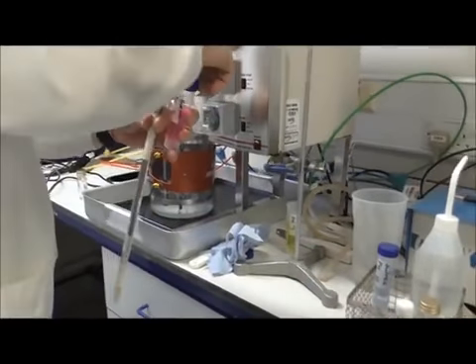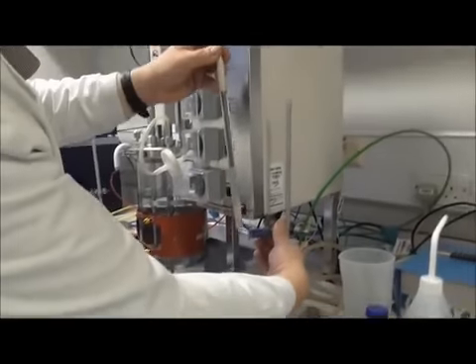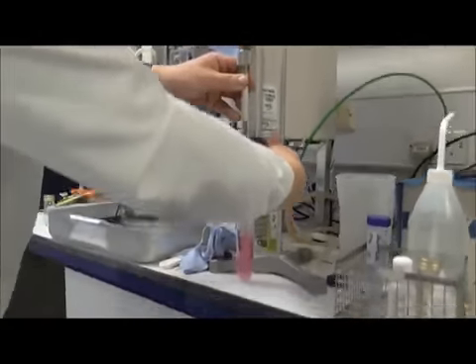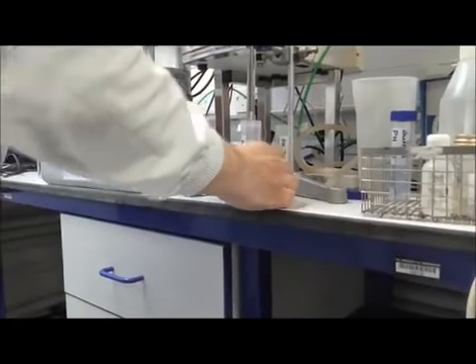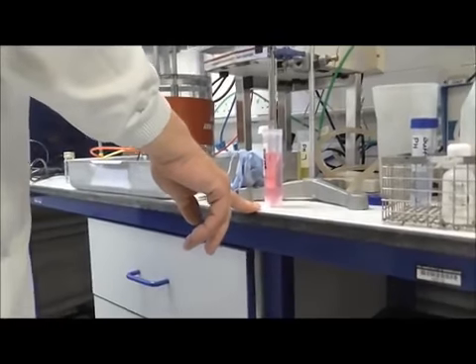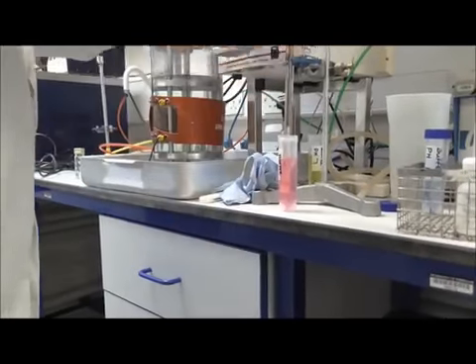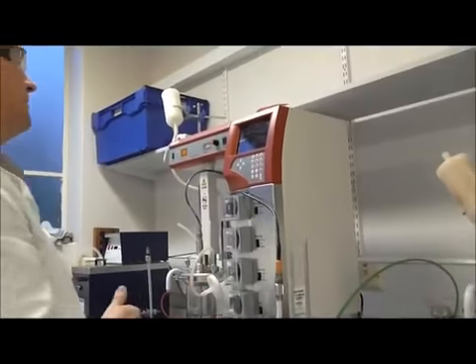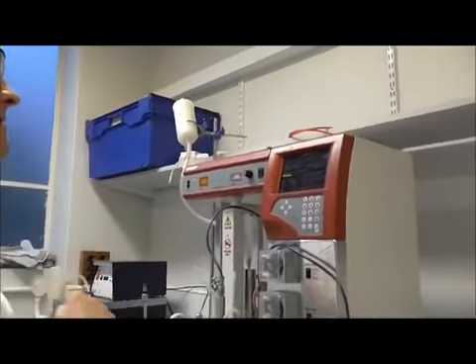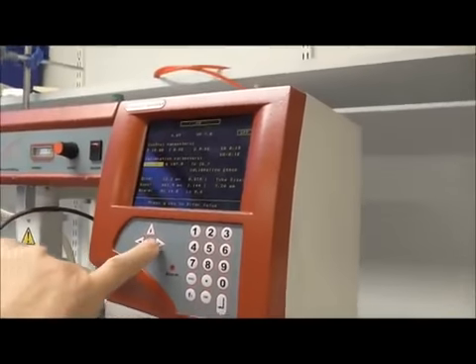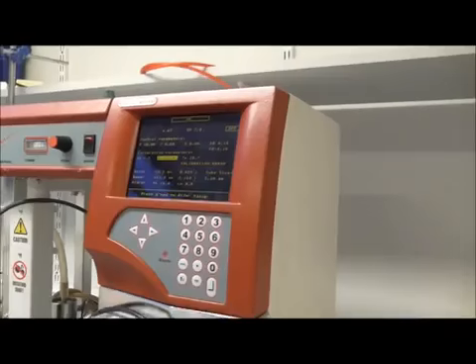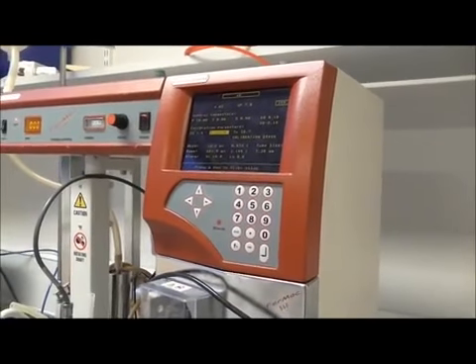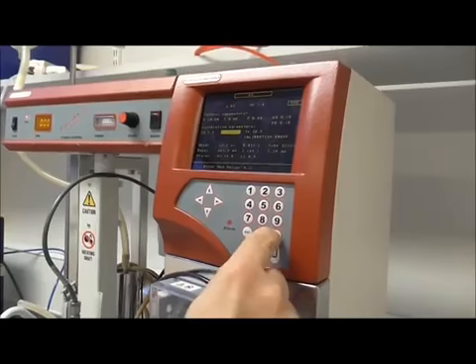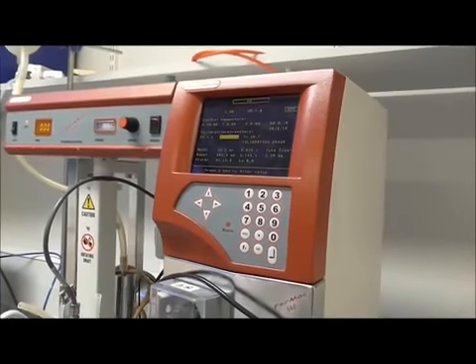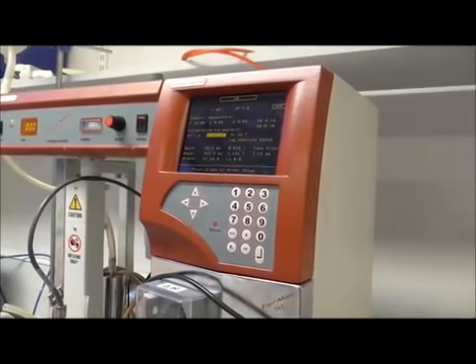We get our buffer number 4. Back into the clamp, lower it in nice and gently. We don't need to measure the temperature of that and input that into the controller because we take it as read that both the buffers have been together in the same room, so they should be at the same temperature. We let our reading stabilise. We're going to scroll the cursor block across to G for gain, and we input, once it's settled, 4.00, enter. And so there we are, we have it confirmed as buffer number 4.